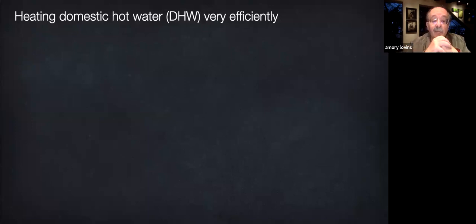Now, RMI's Innovation Center starts not with cold outside air, but with the warm inside air produced by waste heat from the photovoltaic inverters and IT equipment. So a commercial model can cool the closed equipment room down from 25 or 30 Celsius by heating 15-degree cold water to 40 with a COP around 5 or 6. That exceeds the reciprocal of the efficiency of a good photovoltaic module. So after you adjust for system losses, you can actually make more hot water from a square meter on the roof of photovoltaics running such a heat pump than from a square meter of high-quality solar thermal collector.